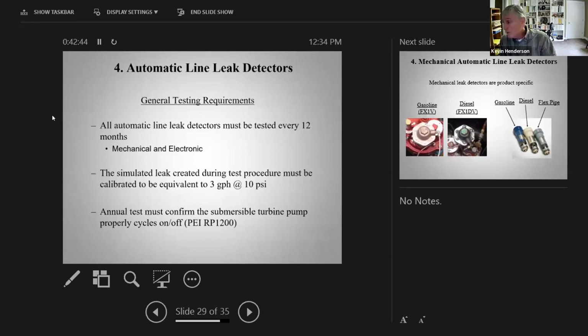Part of the thing that was missing from the annual testing requirement that was made an important part of PEI RP 1200 is that you must confirm that the submersible turbine pump will cycle on and off correctly. That is part of the annual test. If you do not confirm that the pump is cycling on and off correctly, then you have not done a leak detector test.